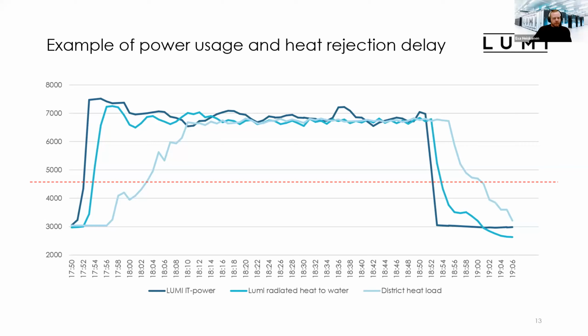Then I have some graph about the delays on the district heating. This red line indicates the point when we have started the third cooling group module. In the beginning, this is actually from this fall when we did Lumi benchmarks. So we had an idle load of about 3 megawatts in Lumi C and Lumi CPU and GPU partitions. And when this HPL run started, electrical power increased very fast, and we are starting these cooling group modules based on the electrical power, not when it's radiated to the water. So the third cooling group module was started immediately when the electrical power increased.